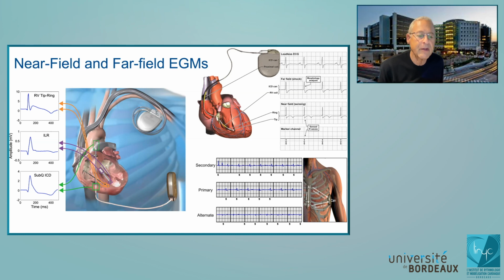Medtronic, the company said, okay, we can basically use a minimally modified version of our transvenous defibrillator and not have to put $20 million into redesigning an entire pulse generator. And so we're going to save money and get something that's an extravascular device. I and others, I don't know how many other consultants, told them, if you use the same filtering, you are going to be in for a world of hurt because the signals have different frequency characteristics. And they do use the same filtering. So the filtered signals are much smaller. They're down around 1 millivolt to 1.5 millivolts on a good day.